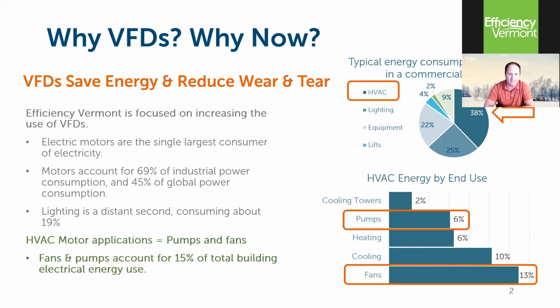And if you break that down further, with the graphic in the lower right, you'll see, combined 19% of that, or about a fifth of the overall building energy is consumed by pumps and fans. And that's kind of the target for our VFDs. We're looking for things that take advantage of the affinity laws. So when you slow a fan or a pump down, a centrifugal load like a pump or fan, you get cubic savings. What that means is if you slow a fan down 10%, you will get about 25% energy savings. So it's better than a linear relationship, which is why VFDs are so cool.